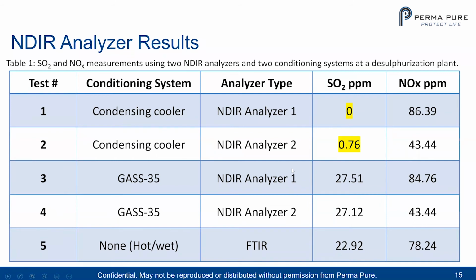So let's look at our NDIR analyzer results. Test 1 and test 2 are using the standard, that's the fixed system in place there, using a condensing cooler. NDIR analyzer 1 shows an SO2 of 0 parts per million and an NOx of 86.39. And in test number 2, analyzer number 2 shows an SO2 of 0.76 parts per million and NOx at 43.44. One of the challenges of showing a measurement of 0, which is actually common in a lot of installations where you have low-level measurements, is that you don't know whether that's the actual reading or the equipment isn't working. Of course, whenever there's a 0, the biggest issue is that most people don't accept the 0 because there's no confirmation that the equipment is actually working. And that's one of the things we always want to avoid in the field. You've got to have some results.